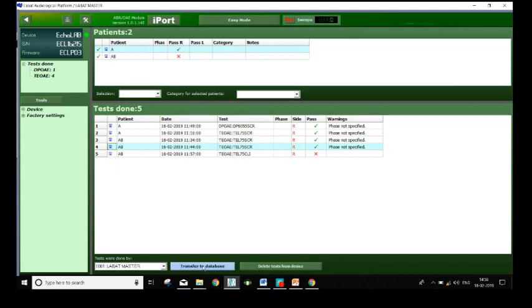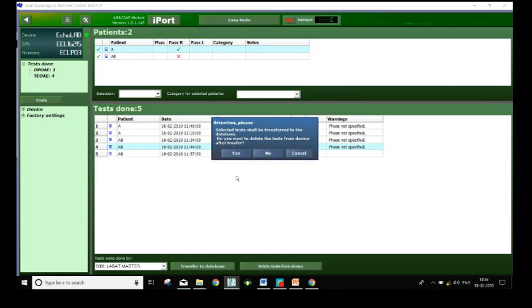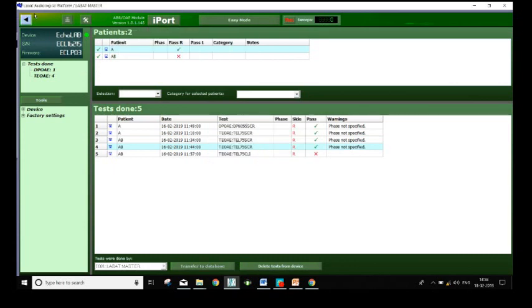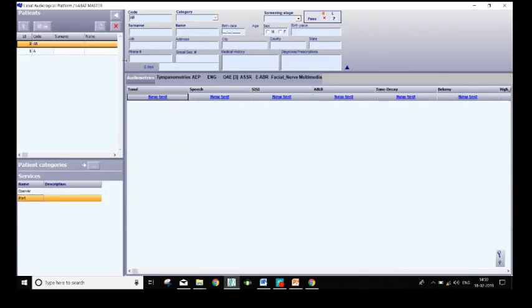You can see now I am hitting transfer to database. It gives me a prompt message that once the test is transferred, delete it from the equipment. So I'm hitting no until and unless I'm sure that the tests are transferred. So the tests are now transferred. You can go back. Now you can see the patient ID is created over here. In order to open the test, I'm selecting this very first one. I'm entering the surname and then the name and then the date of birth. These three details are important, else you will get an error message from the software.